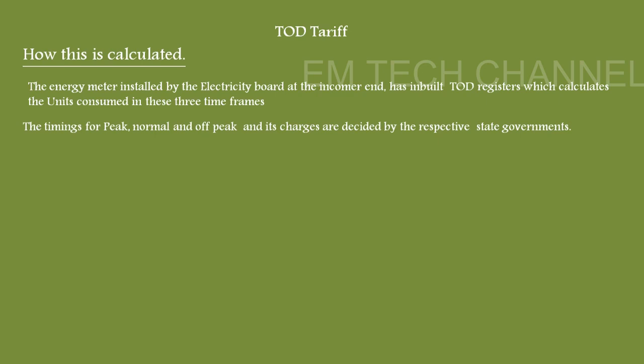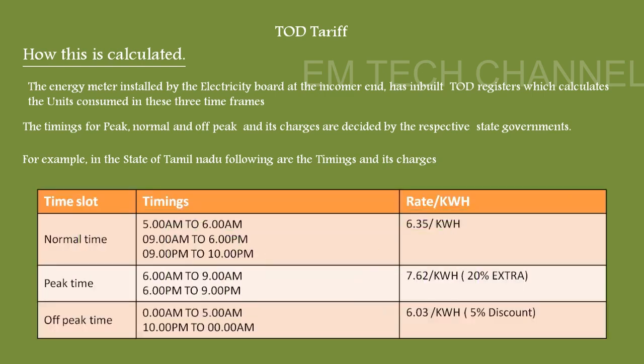In our example we took Tamil Nadu tariff as a reference. You can see the Tamil Nadu tariff rate where timings are divided into normal time, peak time, and off-peak time. Normal time is from morning 5 to 6 AM, 9 AM to 6 PM, and 9 PM to 10 PM, and energy consumed in this period is charged at 6.35 rupees per kilowatt hour. Peak time is from morning 6 AM to 9 AM and evening 6 PM to 9 PM, charged at 7.62 rupees per kilowatt hour — that is 20 percent extra over normal charges.